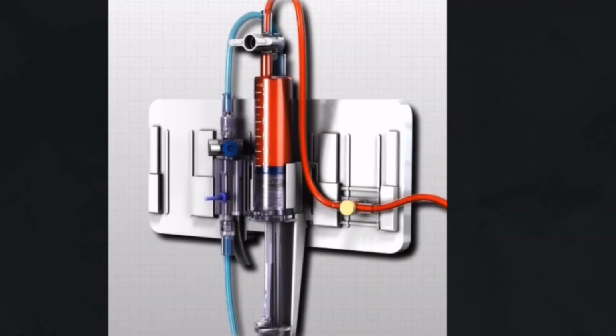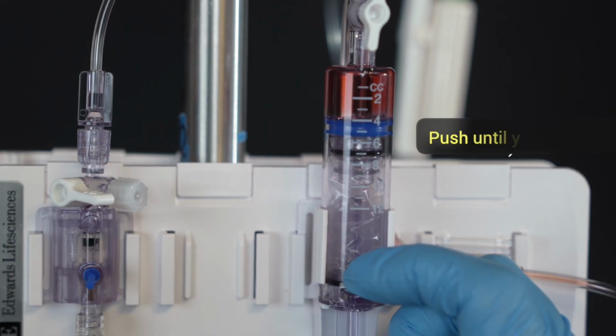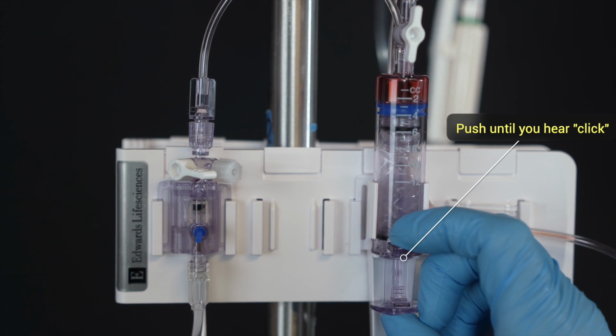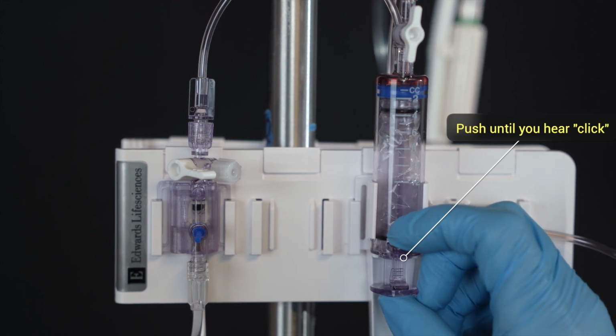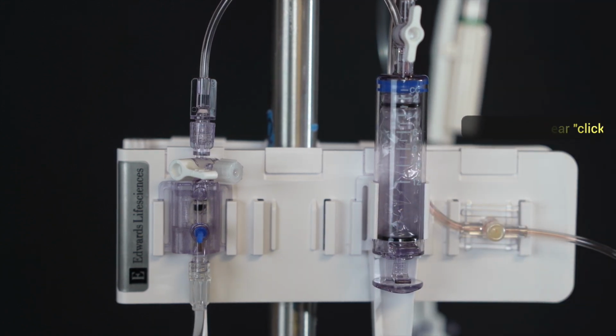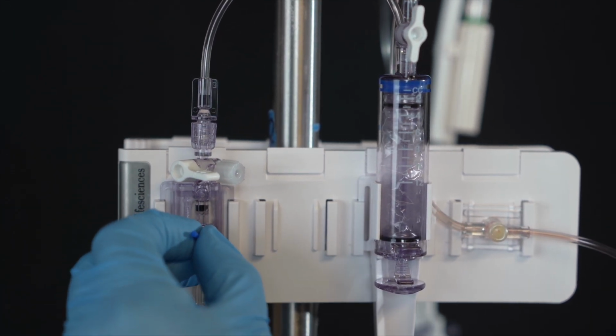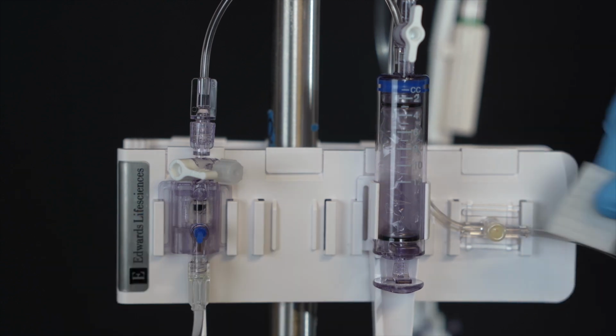When blood has been drawn, remove the vacuum tube first, and then grasp the direct unit by the cannula and pull straight out. Next, you will need to reinfuse the clearing volume. Open the shutoff valve by turning the handle parallel to the tubing. Then, reinfuse the clearing volume at 1 cc per 1 second until you hear the audible click from the plunger. Then, flush the Vamp closed system by pulling the flush device on the transducer and then swab the sample site per policy.